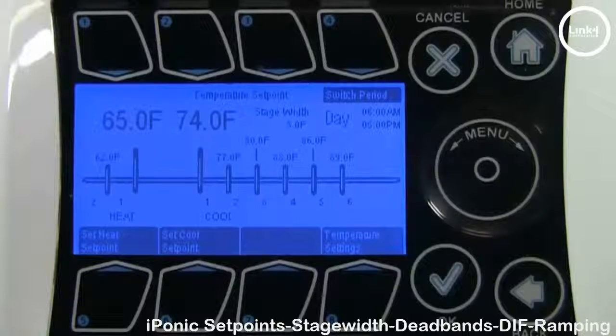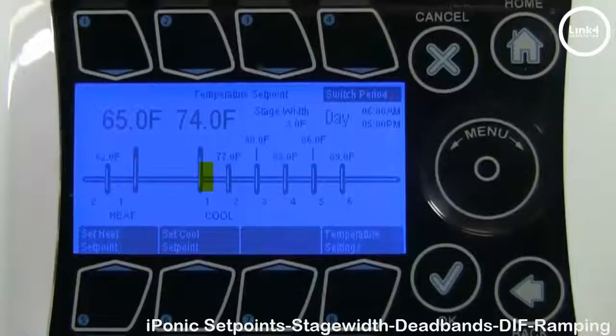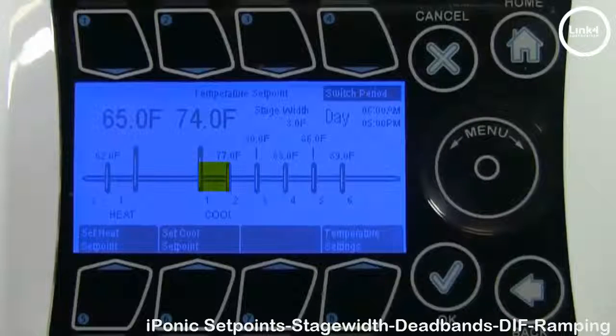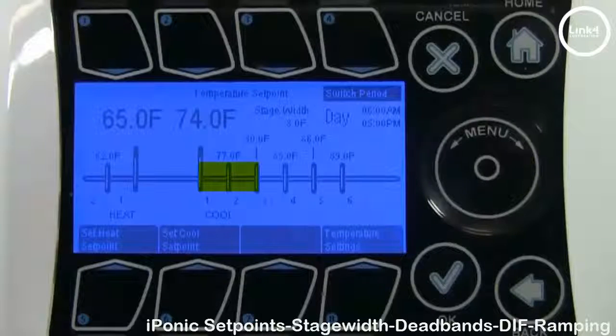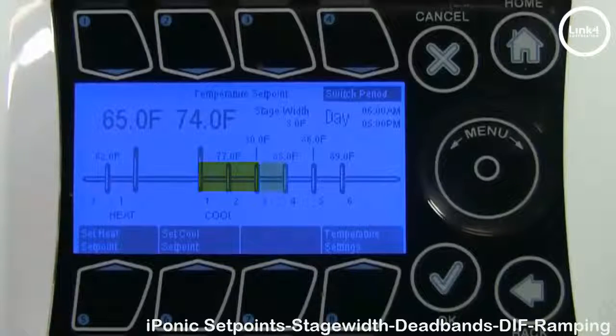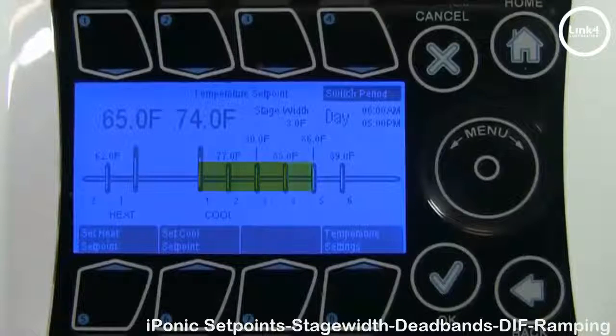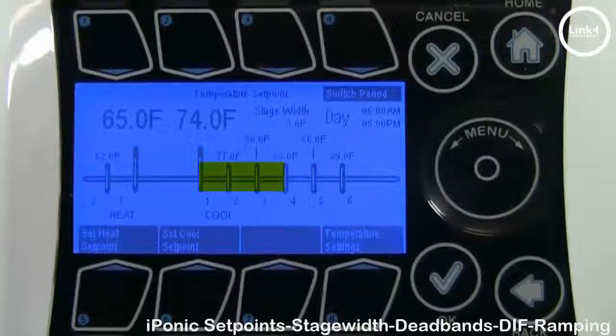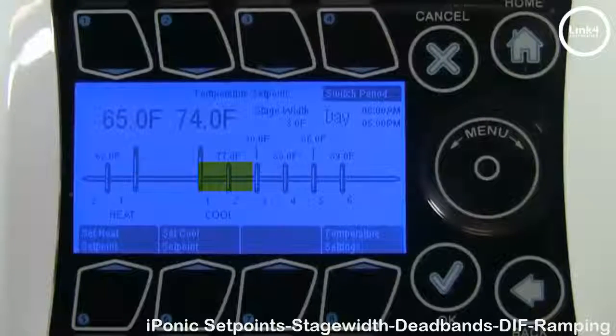If the temp rises beyond the set point of 74, you immediately enter cool stage 1. If it rises three degrees above the set point of 74, the controller will activate cool stage 2. Three degrees higher activates cool stage 3, and so forth, systematically turning on your equipment to counter the temperature increase and reduce it back within the normal set point value plus the dead band.